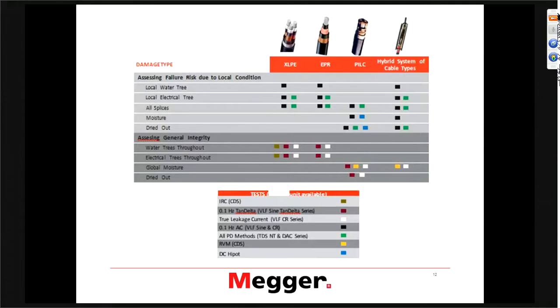On the other side, if you have severe water tree damage in cables — individual really substantial water trees in a local area — they would not show up as a global measurement on the Tan Delta. But they would certainly fail under a hipot condition.